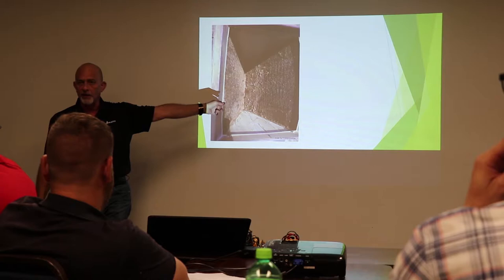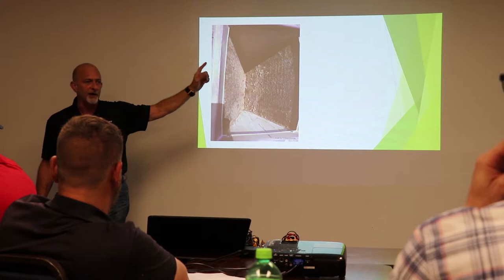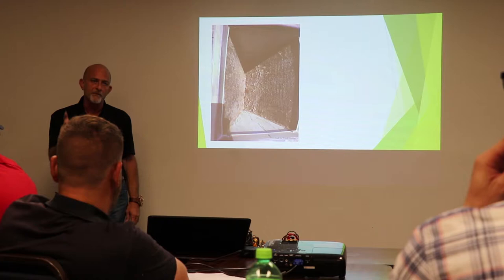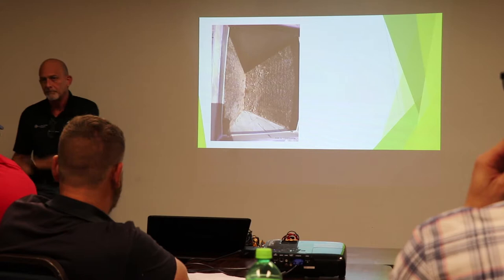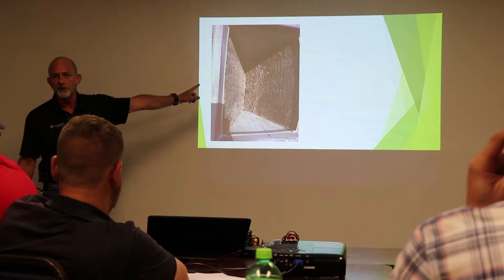Easiest way to look at this, guys, pull out the high limit. Just about every furnace made out there. Upflow. Downflow is sometimes a little harder, but on an upflow, pull out our high limit, take our little wand, bend it up in there, bam. There's the bottom of our evaporator coil. And these people are going to tell you they change their filter every 30 days. Mm-hmm. Right.